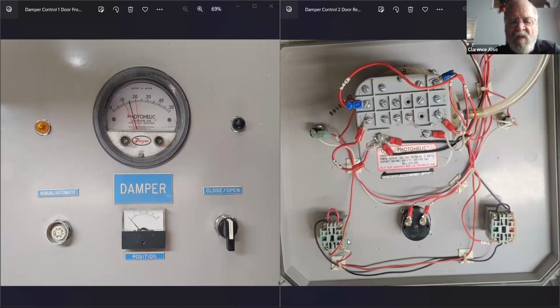Excuse me - going to our actuator. And then you see we've got the manual/automatic switch there, on the far left, with its operator missing. Depending on manual or automatic, it depends what the circuit's going to be doing, but it's picking between one of two things. In manual, you do the close/open; in automatic, you use that photohelic. The photohelic closes or opens some contacts whenever that needle gets on one side or the other, trying to keep this thing balanced to position your damper for what you need.